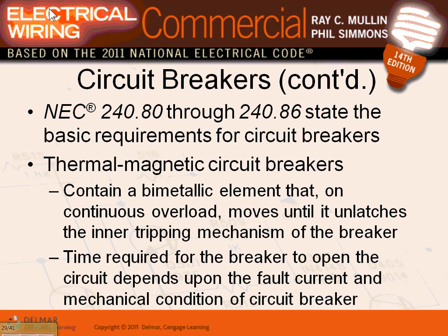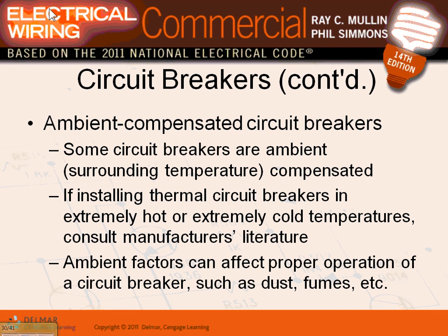If you have bimetallic component, thermomagnetic, you have to be aware if you put them in a hot climate. What happens if you have a circuit breaker tripping and the circuit breaker is in 110 degree Fahrenheit? Would you think that there's a thermal component here? If the ambient temperature is high and it's also pulling high current through it, what is going to make it trip faster? So there's so-called compensation that you have to compensate for the tripping. You have to compensate, making that circuit breaker bigger, basically, so it doesn't nuisance trip. Ambient temperature compensation, that's what we said.